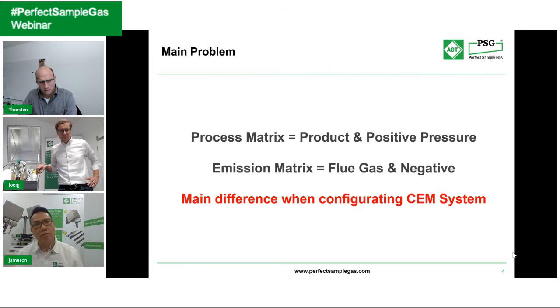I'd like to point out that in process gas matrices, they are all product. Mainly they are clean and at positive pressure. All right, for flue gas, starting from combustion, from DeNOx, from FGD, all the way to CEMS systems, these flue gases generally have a sample pump, which means they are at negative pressure. They need the sample pump to siphon the gas to the analyzer. That makes a big, significant difference when you start to configure a reliable CEMS system.